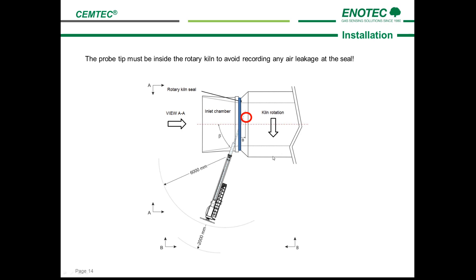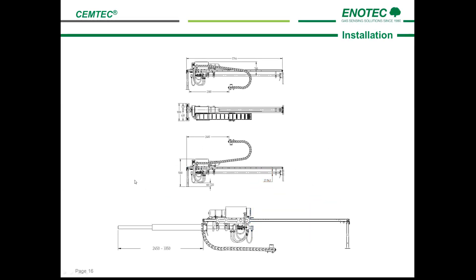As can be seen in this drawing, the insertion angle should be chosen to protect the probe from falling debris from the pre-heater tower. The probe should be positioned at a decline, usually around 2–3%, to prevent contamination inside the probe. Depending on the position chosen to enter into the kiln and the platform itself, the position of the E-chain can vary — it can be placed upwards, downwards, right, or left.